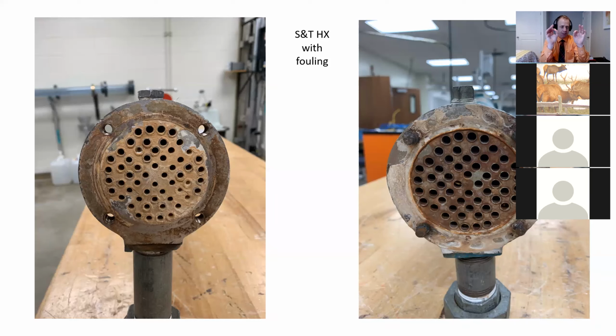Now, having said that, we'll talk a little later about this. You usually put the dirtier stuff on the tube side because it's easier to clean the tubes. Even for this one, I can mechanically put a big wire scrubber down the tubes, and they're 20, 30 feet long, kind of like a really big bottle scrubber, a baby bottle scrubber, and mechanically scrape junk off the tube side. So I usually put the dirty stuff on the tube side, and the cleaner stuff on the shell side.